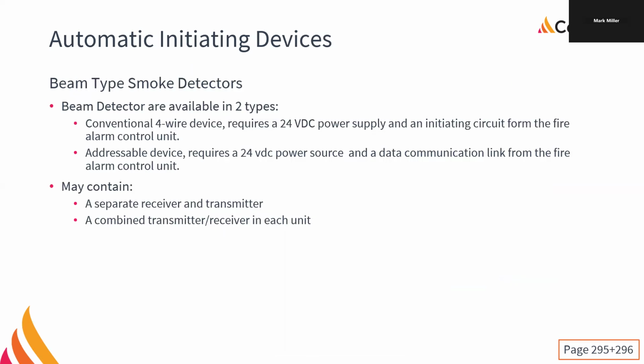For large open area protection, beam detectors are the way to go. They're a lot of fun to install, so long as you plan things out properly, and you always need to bring 24 volt to them. We're going to have the initiating zone and 24 volt because they require a little bit of power. Some of them have two parts. They have a transmitter and a receiver.